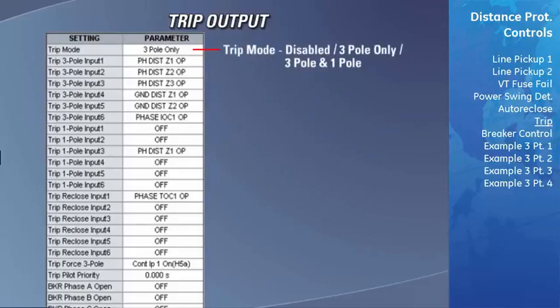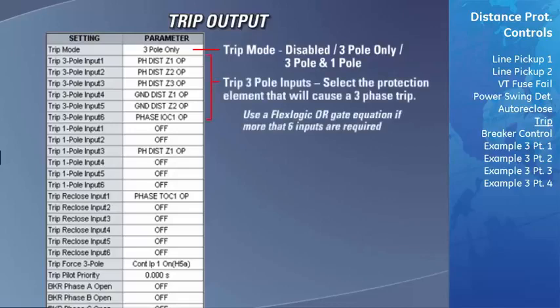3-pole should be selected if you want to trip all 3 phases for all faults. 3-pole and 1-pole should be selected if you would like to have the ability of tripping only one of the phases when a single phase-to-ground fault occurs.